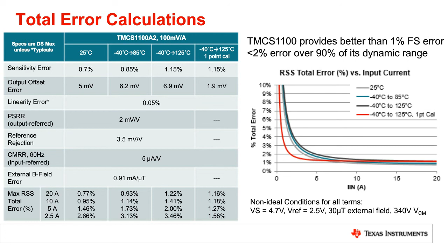Okay. Some current sensors I've used have a ratiometric output. When should I use a device with a fixed versus ratiometric sensitivity? So a ratiometric device simply means that the sensitivity changes with supply. Where this works really well is in systems where the analog supply to your sensor is the same as the full-scale reference to your ADC and is expected to vary widely. That way, if that supply changes, your sensitivity matches your ADC scale change.